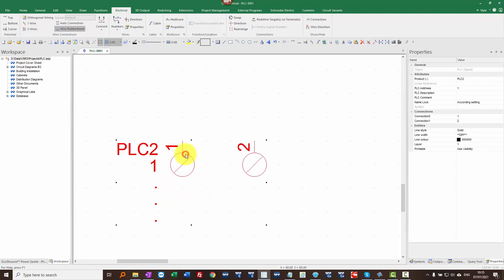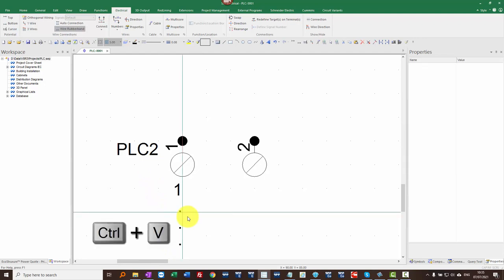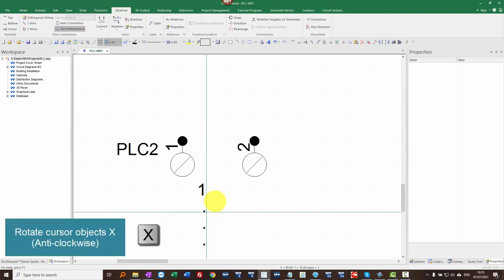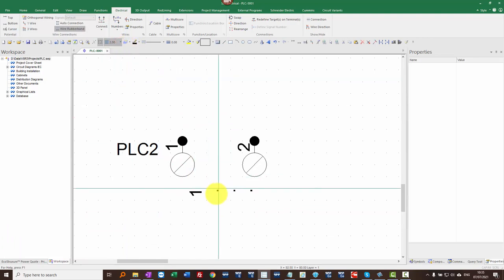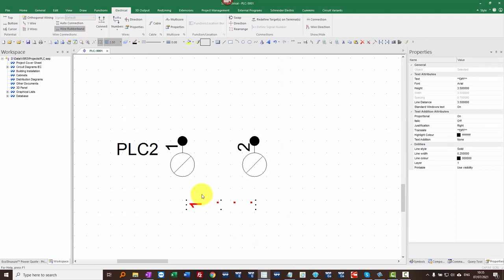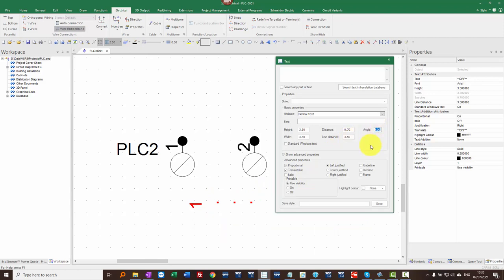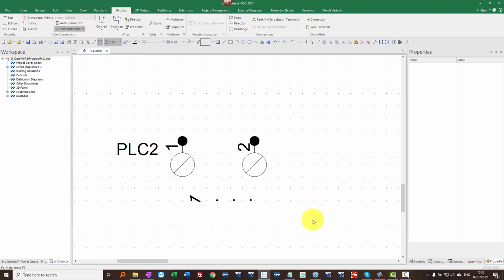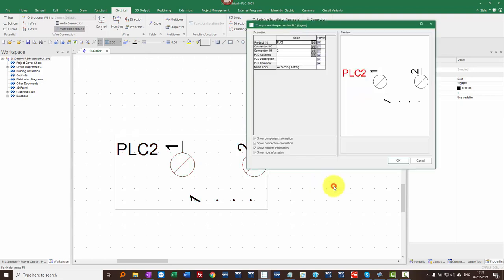Now I'm going to move the address text and the description. I'm going to explode it and window around those bits at the bottom. I'll use Ctrl+X to cut, Ctrl+V to paste, and once something's on my cursor, I can use X and Z to rotate. So I'm going to use X, rotate that a little bit, drop it onto a 2.5mm grid, and drop it in between those two. I'm going to select those bits of text — they're already right-hand justified so they'll work down the page. I'll use Ctrl+E to edit the text and select a 60-degree angle to make it a bit easier to read front on. That's my PLC signal done. I'm going to window around it and block it again as a PLC signal. It doesn't ask me for anything else — it's got all the information it needs. I'll click OK and that's done.